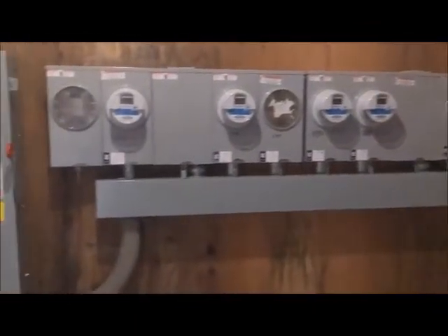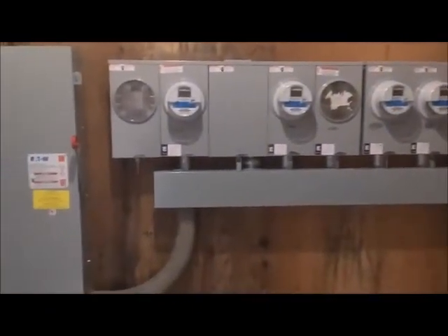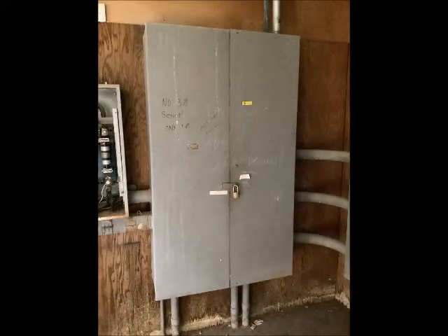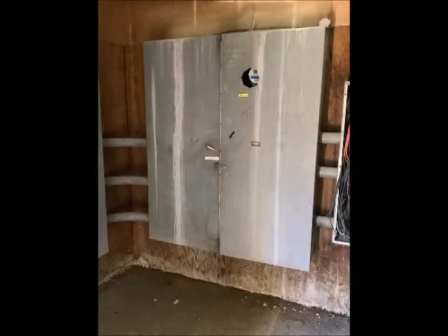We've got two four-position meter banks. We only used six spaces — we've got six inspections. The meter bank on the left end is a blank, that's a spare, and the meter space on the right end is a spare. Six-inch gutters, six disconnects there, three-inch 90s. We used the 90s from the old setup. Big 18x18 J-box, and we used this big old panel for a J-box — three-inch EMT.